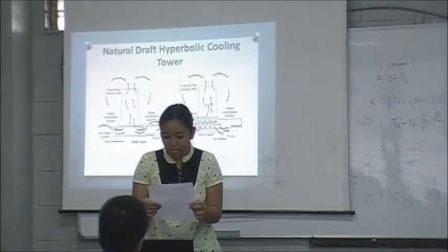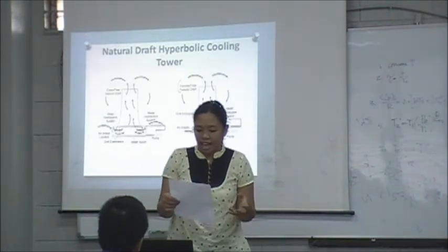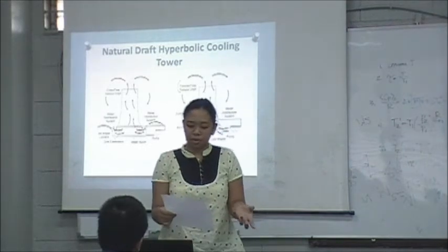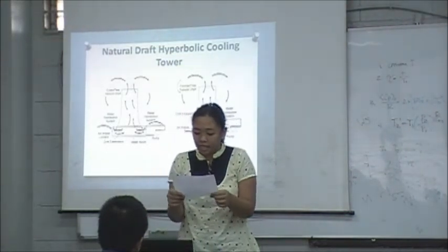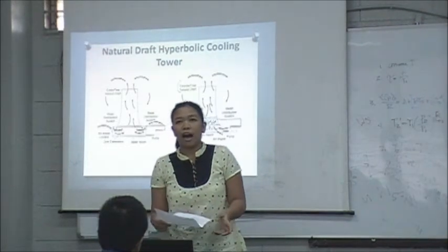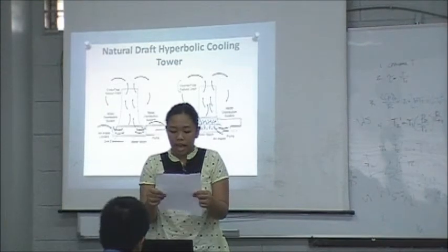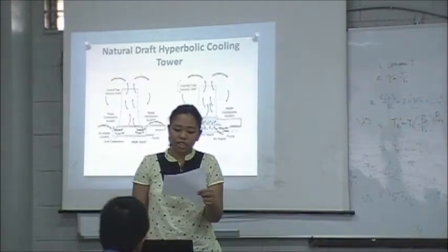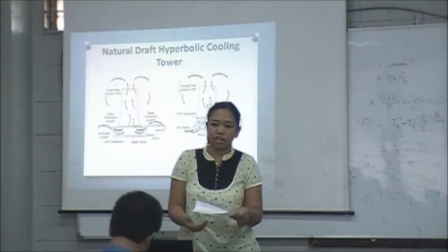And with the fan being at the inlet, it becomes more susceptible to complications due to freezing conditions. That's why it is usually located inside or installed indoors.